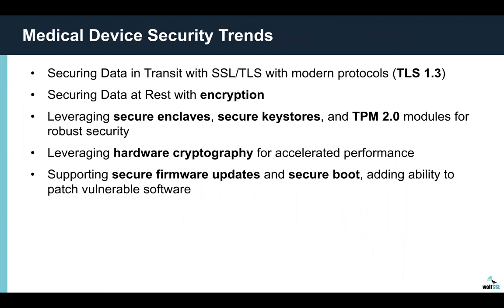Some of the trends we've seen with medical device customers: they want to secure data in transit using TLS with modern protocols, and TLS 1.3 is the latest version available today. They're looking at securing data at rest by using encryption. We see a lot of customers who want to use secure enclaves or secure key stores, which could include a TPM 2.0 module as an extra layer of security for key storage. We see people wanting to leverage hardware-based cryptography, which gives them accelerated performance, typically at least 5 to 10 times on embedded platforms. We also see people wanting to support secure firmware updates and secure boot, which adds the ability to patch vulnerable software and extend the lifetime of your device.